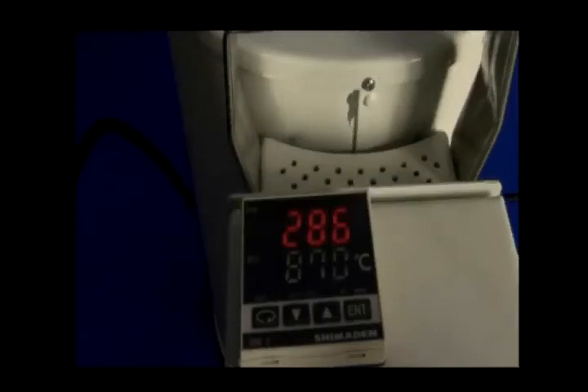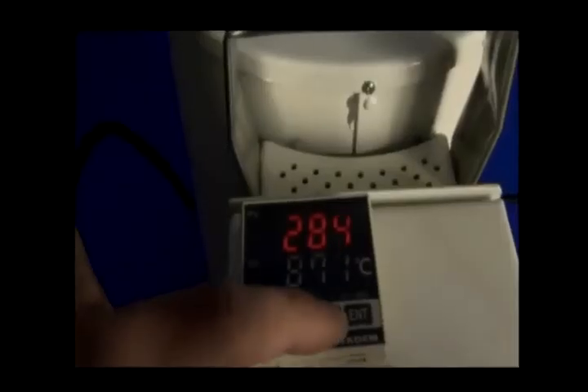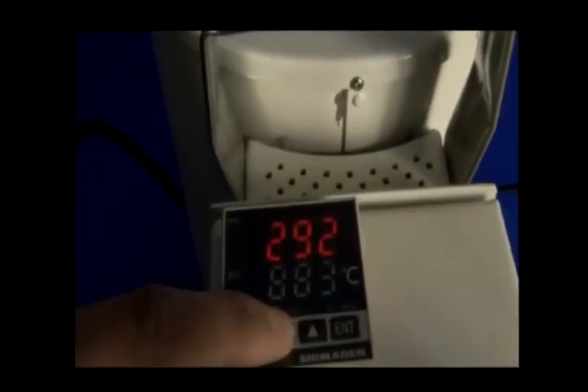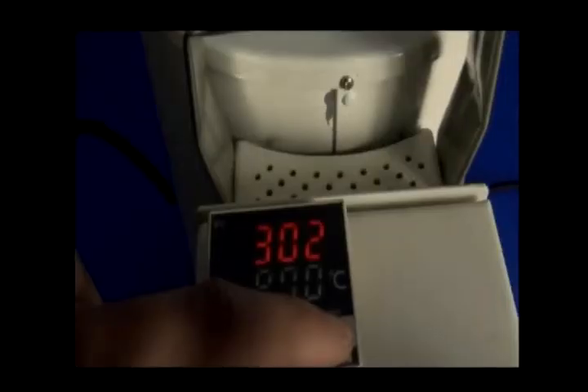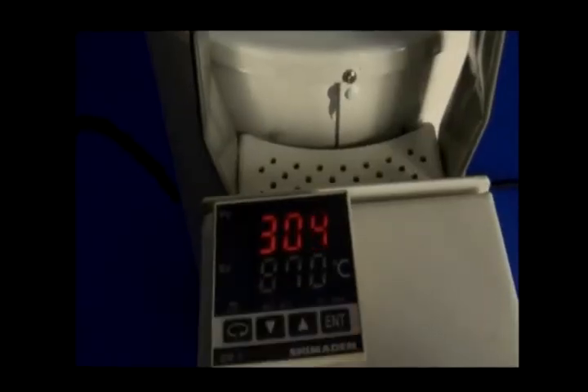Set the heating parameter of the furnace as well. The temperature of the furnace has been calibrated to a constant when leaving the factory, about 870 centigrade. You needn't preset anything when you make a normal test. If you want to set another temperature, please set as follows. Press up to raise the set temperature. On the contrary, press down. Press ENT to confirm after setting the temperature you need. Normally, you'd better not set the temperature too high, as that will damage the furnace.